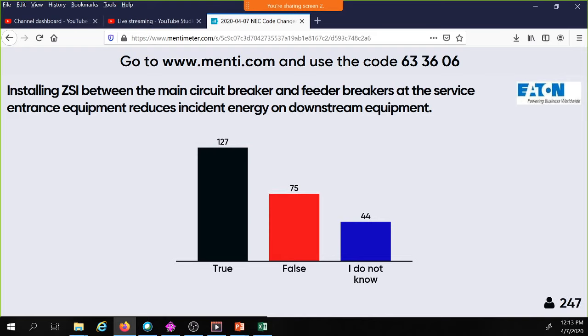Zone selective interlocking detects arcing and sparking. It detects when fault currents go into the zone, but don't come out of the zone of protection. So they provide protection when faults are in the zone of protection. Now, I can layer zones of protection. I can extend the protection of ZSI downstream by increasing my zones of protection, yes. But when it's in this service equipment, connecting the main with the feeder breakers or branch breakers in that equipment, you're only protecting the bus in that equipment, not anything downstream.